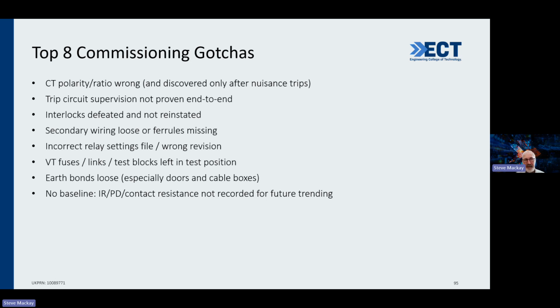But basically, I was just being difficult there. I think it's very unusual. If you've got a critical circuit breaker and you want to trip it, you would probably have a separate DC power supply from a separate battery, or you would make sure you can trip upstream. The biggest problem, obviously, is that when you're tripping your breaker, you've got a 30 millisecond, say, tripping time. If you're tripping further upstream because the one's failed, you're probably looking at 100 milliseconds or longer. It depends on your installation, so it's probably not as good a solution. So obviously, checking your DC power supply always is very important.